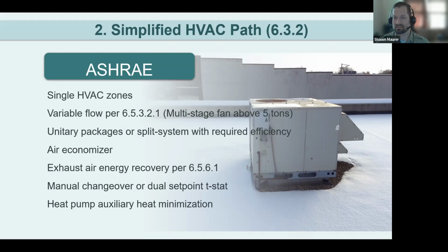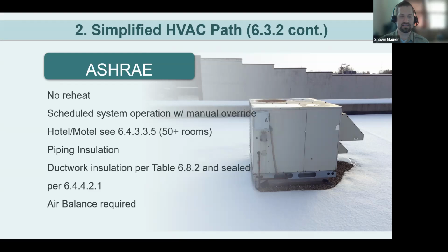Many of these systems are going to qualify for this given their sizes. If we think back to what was mentioned about right sizing equipment, it may help the system meet requirements for the simplified HVAC by reducing its size when you replace it. Just as an example, if you take a 7.5 ton system, properly size that piece of equipment during the upgrade, and it gets reduced to a 5 ton unit, improvements such as lighting upgrades or more efficient computer equipment might help reduce the load in the building so that you can downsize that equipment. Not only is that 5 ton unit going to be less expensive than putting in a 7.5 ton unit, but that new one can use a single stage fan, which saves you even more in your upfront capital costs. And the reduced airflow may also bring the unit under the threshold to require energy recovery. So it's nice that ASHRAE breaks this out and lets you consider it as a separate compliance path. It's easier to reference than going through the full compliance options in the 6.4 section of ASHRAE.